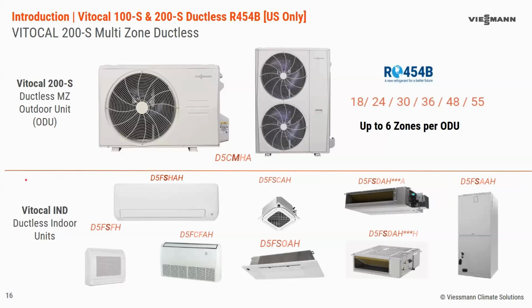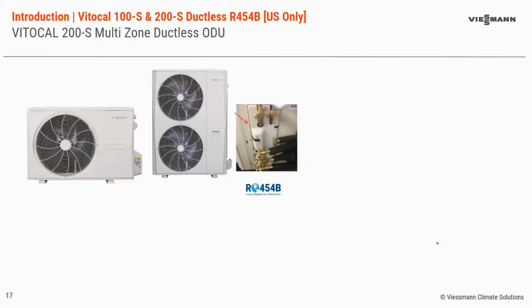The indoor units are the same as what's used on the single zone residential. So that's something to call out, to note that there are not special high walls or any special indoor units dedicated to multi-zone. So that's easy to maintain, whether you're keeping stock or ordering systems, preparing systems, just to know that it's all the same between single and multi-zone, with the exception of the light commercial.